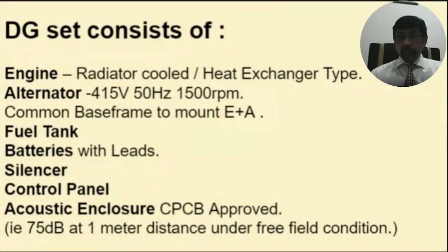Now, what is an engine? Engines are of two types. One is the radiator cooled engine and one is the heat exchanger type. Radiator cooled engines are the engines fitted with radiators, where the cooling medium is coolant. The radiator is filled with coolant. And in certain industries where there are fluffs or cotton threads moving and choking the fins of the radiator, we use the heat exchanger type. Or maybe in a basement where you cannot have a draft of air coming out of the radiator, as it does not have any passage to go out. So there they go for a heat exchanger, especially if you are installing a generator in the basement.